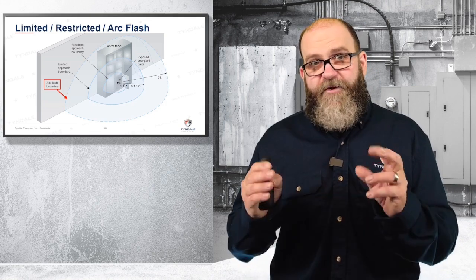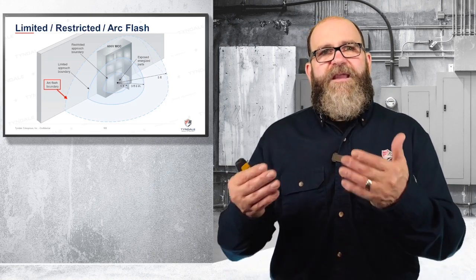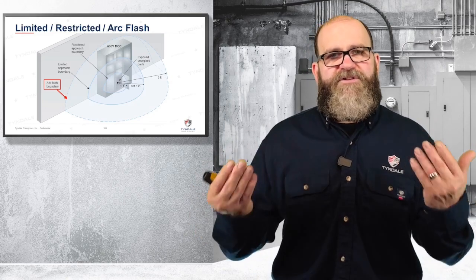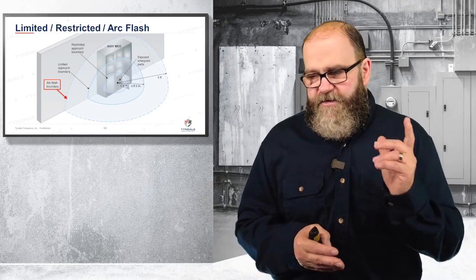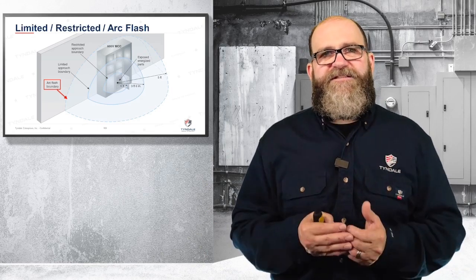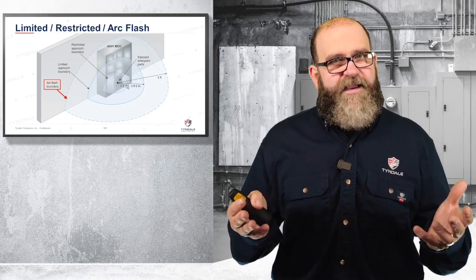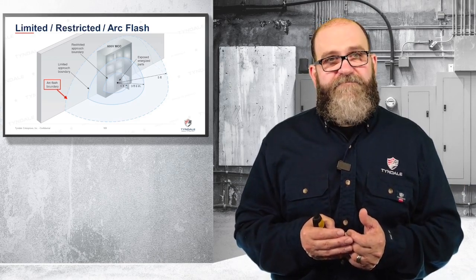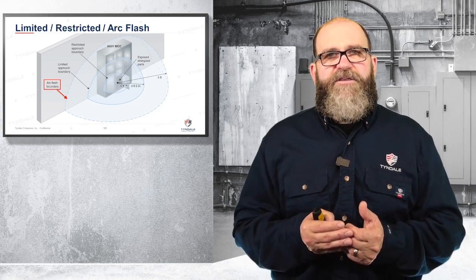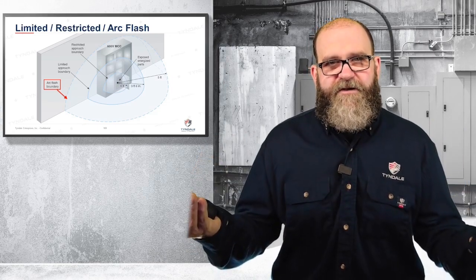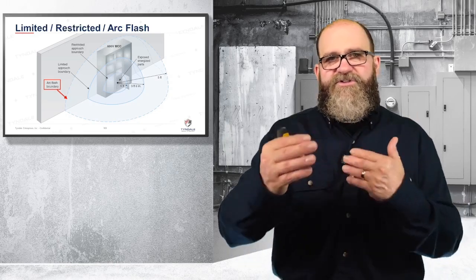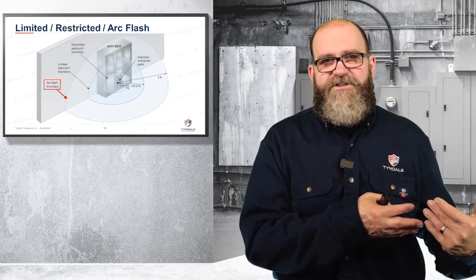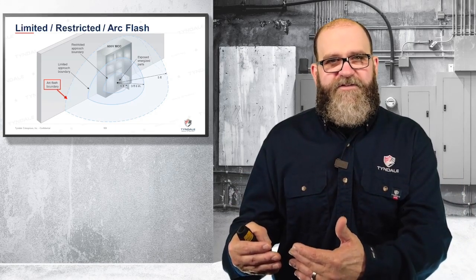So if your arc flash boundary, the imaginary line, is at nine inches and your limited approach is at 42 inches, you will be setting your physical barricade at 42 inches. Now, the same MCC — let's say your limited approach boundary is at 42 inches and your arc flash boundary is at 65 inches. You are going to set your physical barricade at your arc flash boundary. You're never going to be less than the greater of those two. The arc flash boundary or the limited approach boundary — whichever one is bigger, that's where you set your physical barricade.